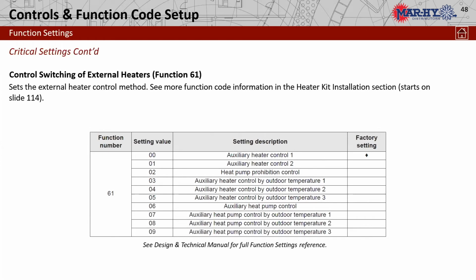Function code 61. This is what sets the format for the strip heat function. There's many different variations to how you can bring strip heat on, whether you want strip heat to be primary and the heat pump secondary, or whether the heat pump is primary, strip heat secondary, whether we're controlled by outdoor temp, whether we want to lock out our heat pump altogether. So I have gone through this, and I have come up with my own codes that seem to work the way that we are used to seeing heat pumps work.